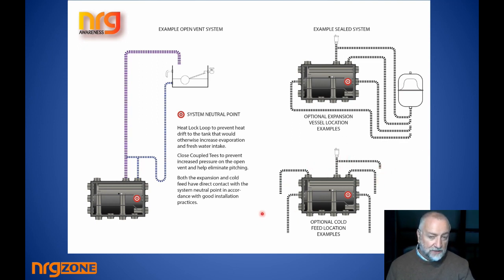You typically find when you put on an NRG Zone system that unless there's something mad wrong with the pipework, if the pipeworks are put in anywhere reasonably right, rising towards the radiators or rising towards any high points in the system, then you'll find that the core system vents itself in 1 minute, 2 minutes maybe maximum, depending of course on the size of the job, but typically they're extremely rapid at eliminating air from the system once the water contents are in. I don't mean that you can fill all the water into a system. I'm talking about deaeration.